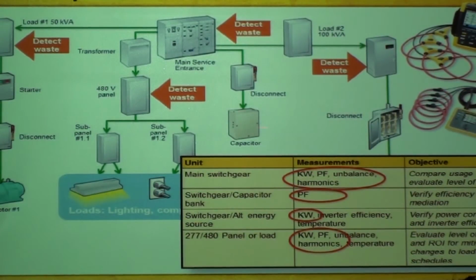So, following up with electrical measurements. Once you do a thermal image, you find out harmonics, you find the neutral conductor hot, that's telling you you've got a problem with the harmonics. How do you verify that? You plug in your power quality meter to verify. What's the condition there? How much harmonics do I have? Do I have any over or unbalanced conditions? Power factor, kilowatts, all these can be measured. So it's sometimes a combination of more than one tool. Unfortunately, as maintenance engineers, we would love to have one tool that did everything for us, right? But it's not always possible. Sometimes you need different tools to do your work.